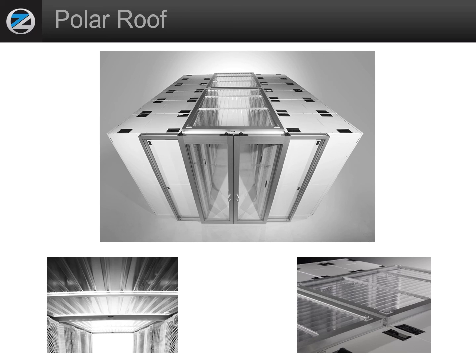It has a modular design to attach to any SubZero door or wall system, and they're designed to attach vinyl or hard wall material for missing cabinets or space. They also drop out at a lower temperature than what triggers your fire suppression system. Once the heat exceeds 135 degrees, these will drop out, allowing your fire suppression, when it activates at 160, to have no encumbrance filling the space with the fire suppression material.